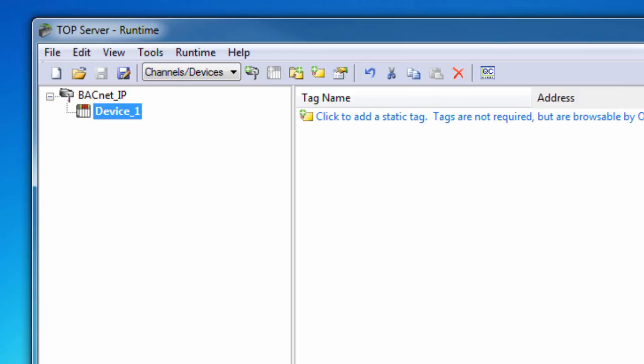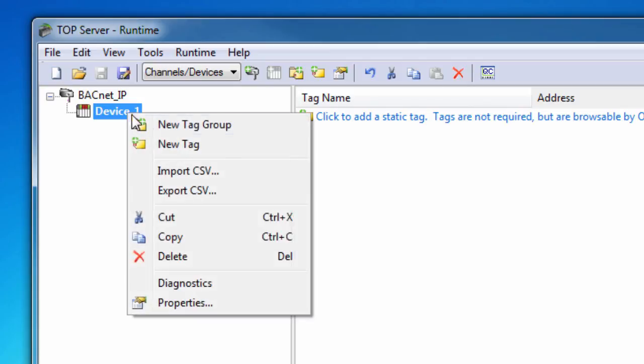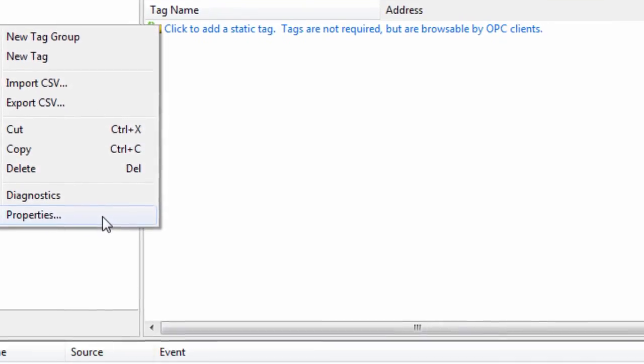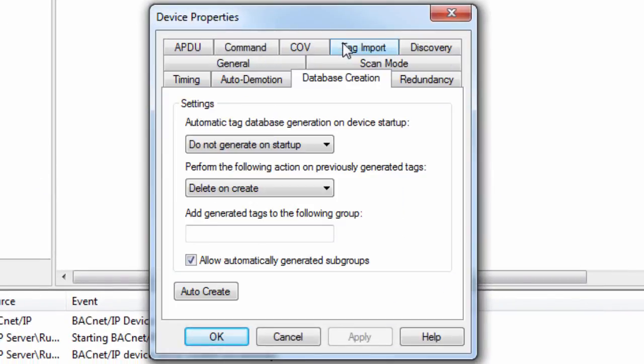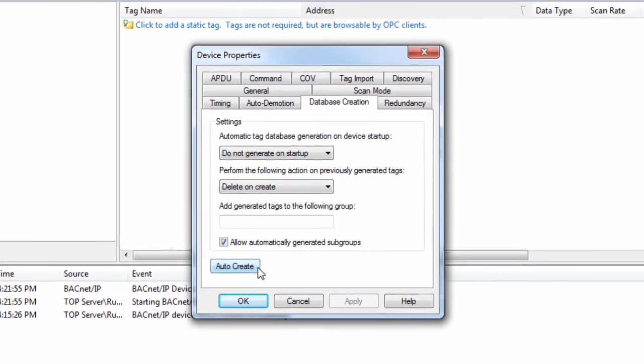Tags can either be accessed dynamically from your client application or using a static address in the server. Static tags can be generated manually or generated automatically using the database creation feature. To auto-generate the tag database, go to the device properties and navigate to the database creation tab. Clicking the auto-create button will generate static tags in the server using the addresses in the controller or import file.